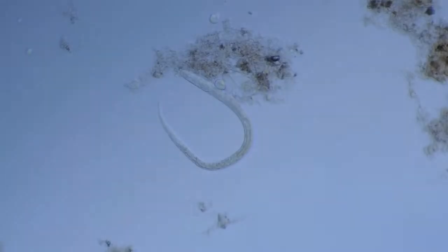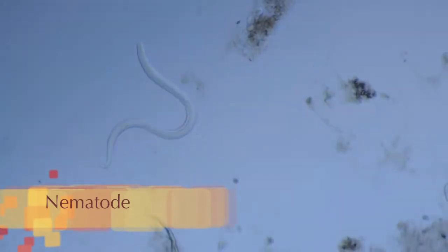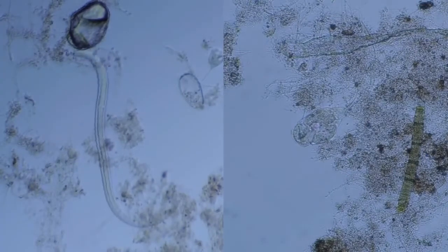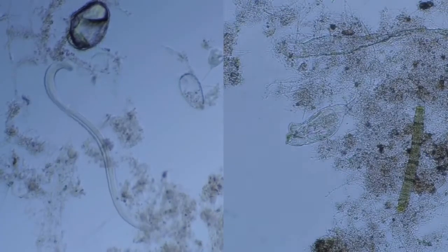Now our worm friends, the nematodes. These tiny worms, who can be active or just swimming lazily around the neighborhood, can also be an indicator of some certain conditions. Both nematodes and rotifers can be indicative of an older bacterial biomass and, in wastewater, are indicative of a higher degree of purification or seeding from an attached growth system.